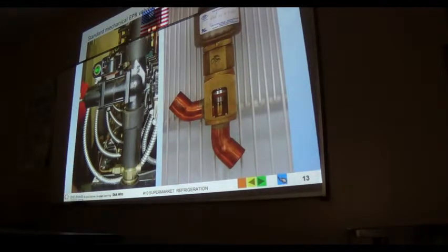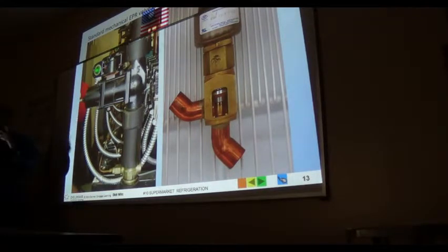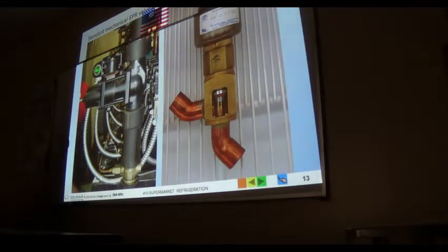When you were doing metering devices, if you remember rightly, you were told that automatic expansion valves behave contrary to what they're supposed to do. As the load is added to the box, that valve actually throttles refrigerant down and starves the evaporator. Whereas the thermal expansion valve would open fully because the sensed superheat is higher than normal. It's going to try like hell to keep a constant superheat. So the automatic expansion valve is one of those backward valves. Bear in mind they work well in constant temperature systems.